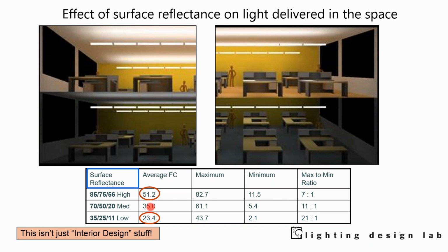But when you go out there for the big ribbon cutting, you turn on the lights, it's really dim in there. You're down, there's a big difference between 35 and 23. Everyone's like, boy, this isn't really what we expected. That's because maybe the customer has a wood ceiling. Maybe they've got saturated colors on the walls, or maybe they have brick, and they've got stained concrete floor, or they've just got a dark carpeting. It could go the other way.